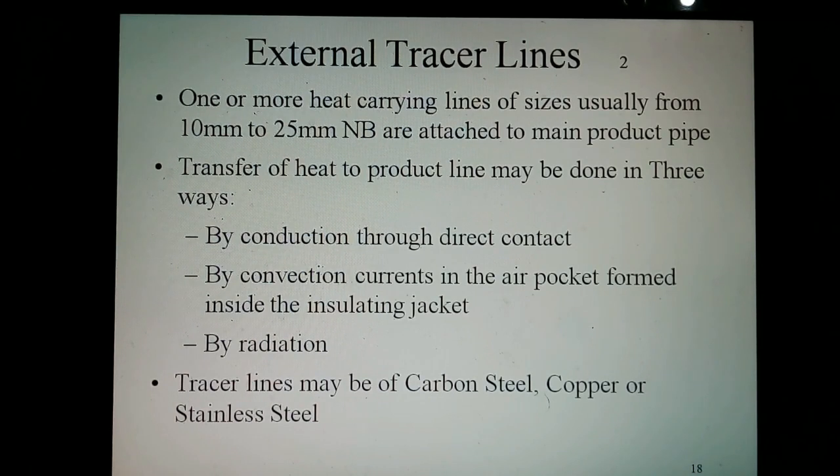Many large users and contractors have their own in-house rules for tracer lines, but the following guidelines may be useful in other cases. External tracer lines: one or more heat-carrying lines of sizes ranging from 10 mm (3/8 inch) up to 25 mm (1 inch) nominal bore are attached to the main product pipe. Heat transfer to the product line may be done in three ways: by conduction through direct contact, by convection currents in the air pocket formed inside the insulating jacket, and by radiation. The tracer lines may be of carbon steel or copper, or sometimes stainless steel.